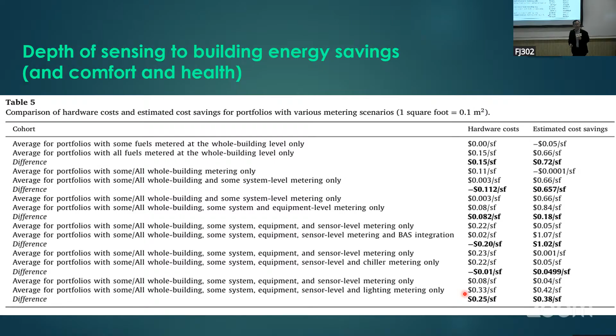The general conclusion is that overall, a whole building sensor is needed. Going beyond that doesn't help you unless you have a BAS, building automated control system. That means when something's wrong, automatic control adjusts it. For example, a lighting sensor detects nobody in the room and turns the lights off automatically. If you rely on a person to turn off the lights, that's not reliable, and you get no benefit. So our conclusion is high level monitoring is good enough. Without a BAS, don't go deeper, it doesn't give you any payback.